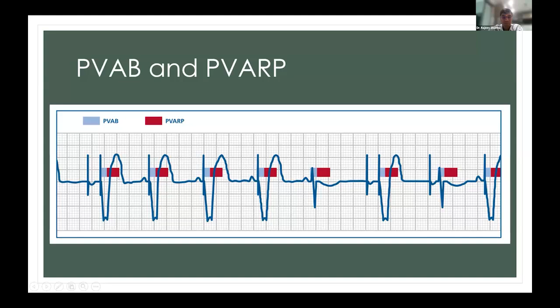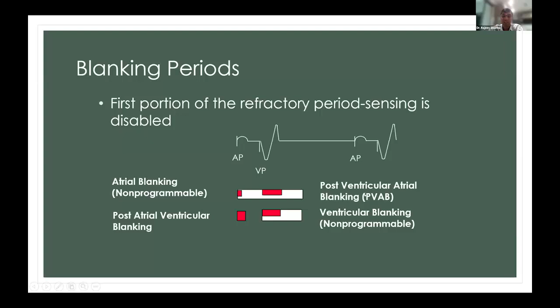After atrial pacing there will be post-atrial ventricular blanking, because the atrial impulse, the pacing spike, can be sensed in the ventricular channel, and that can lead to pacing inhibition. So there is blanking after atrial pacing for the ventricle, and there will be post-ventricular atrial blanking similarly, to prevent crosstalk. Then one more term, that is total atrial refractory period, TARP.